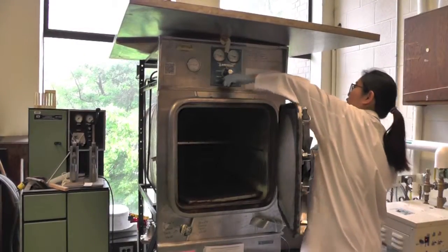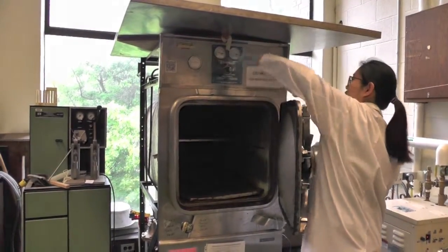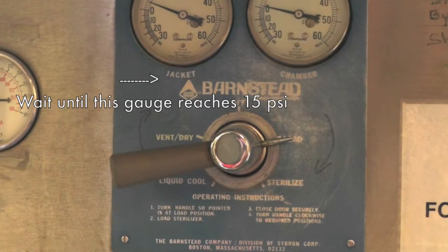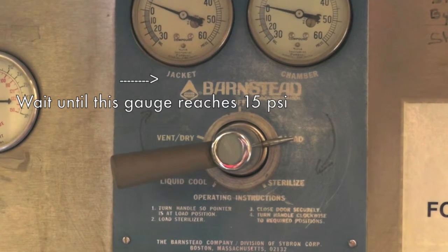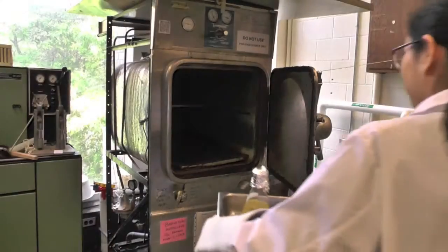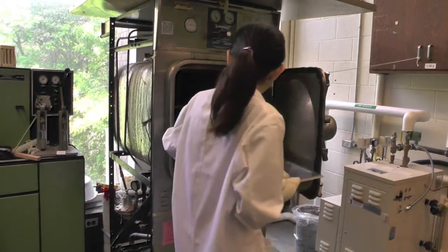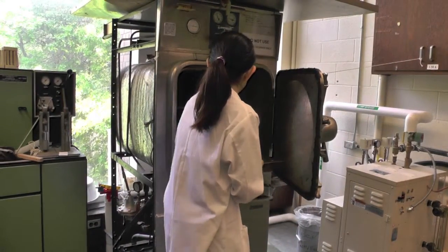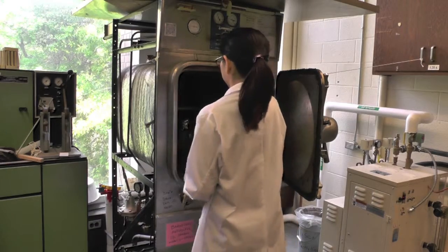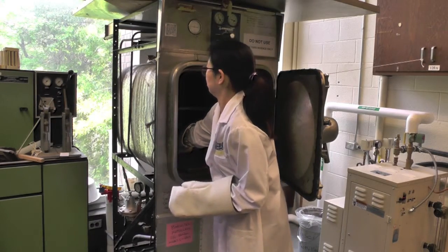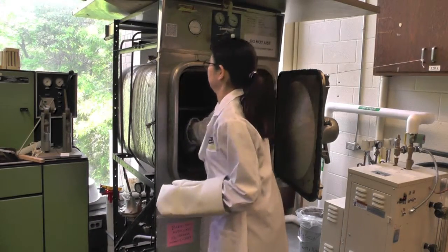Then on the autoclave, turn the knob to load position. Wait again for the jacket gauge of the autoclave to reach 15 psi. Now you can put in the materials that you want to autoclave. You must place all items in a large metal tray to avoid any spillage into the main autoclave compartment.